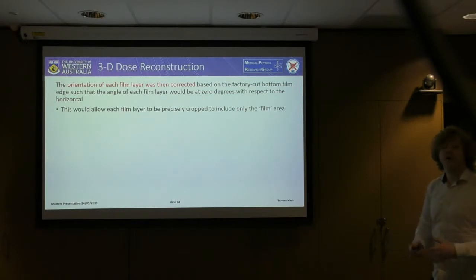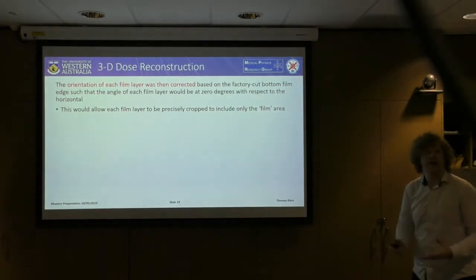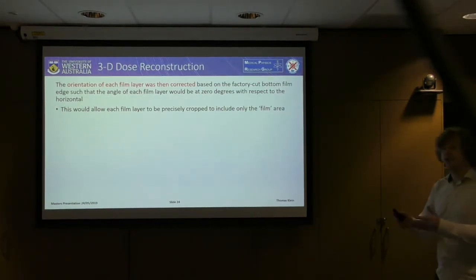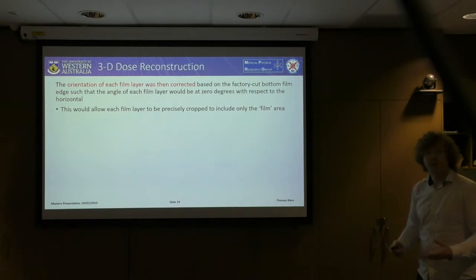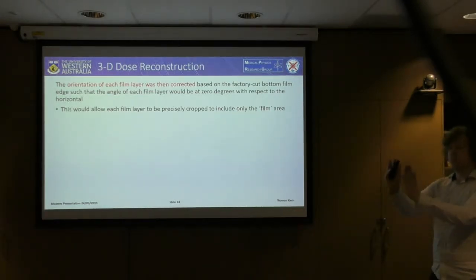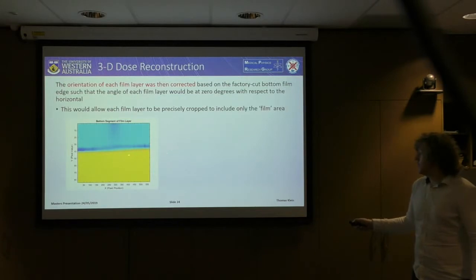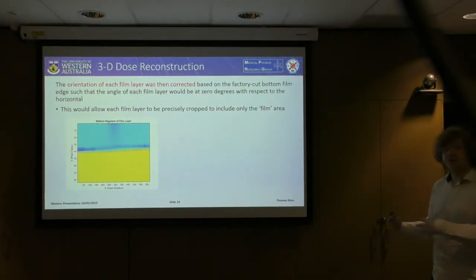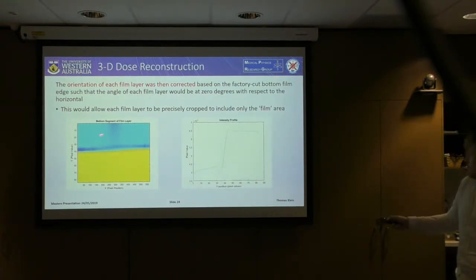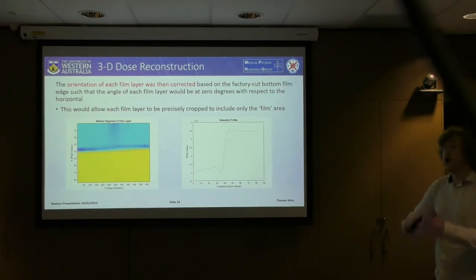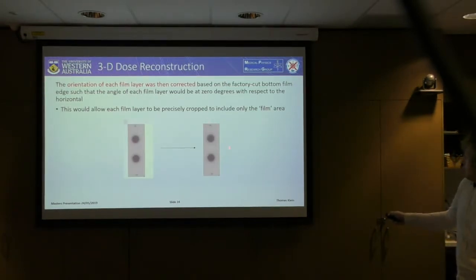When scanning the films, it's not reasonable to assume every film can be scanned in the exact same orientation, yet precise cropping to include only the film area is essential. Consequently, as each film layer was read into MATLAB, we wrote an algorithm to correct the angle so each film was normalised to lie at zero degrees with respect to horizontal. This was achieved by taking a rough crop of the bottom factory edge for each film layer, taking a vertical intensity profile for every column, finding the central point, and plotting a line through all such points to determine the angle — then correcting and cropping the image.